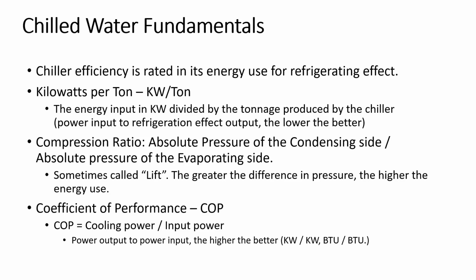Okay? So we use kilowatts per ton and how much energy we put in divided by the tonnage produced by the chiller. And we'll talk more about this later on, but it's power input to refrigeration effect output. The lower this ratio is, the better. 2 to 3 kW per ton. We'll take a look at that later on.